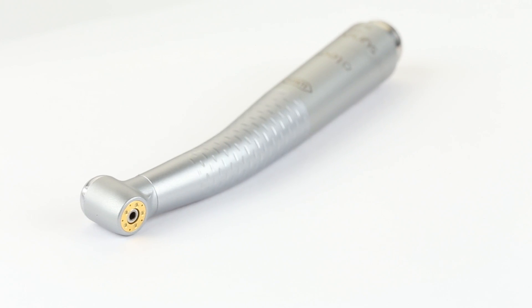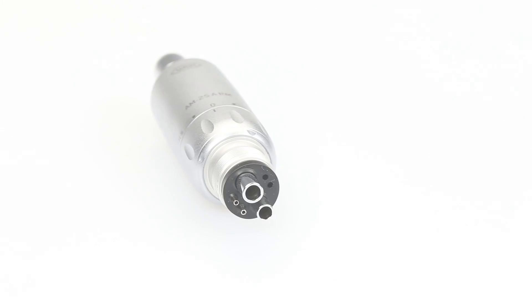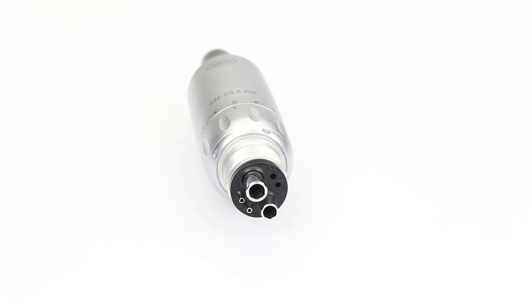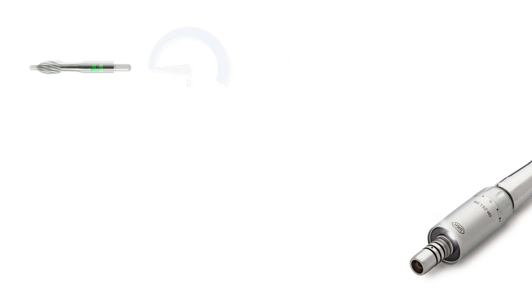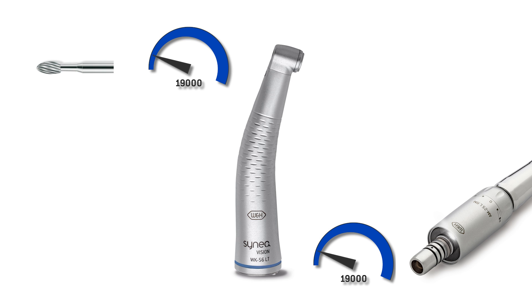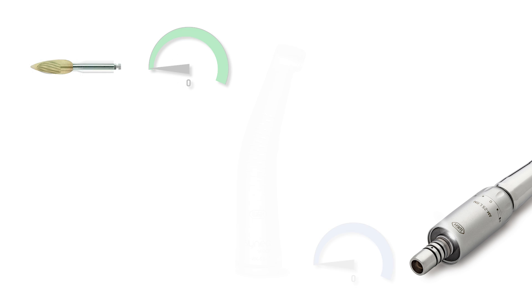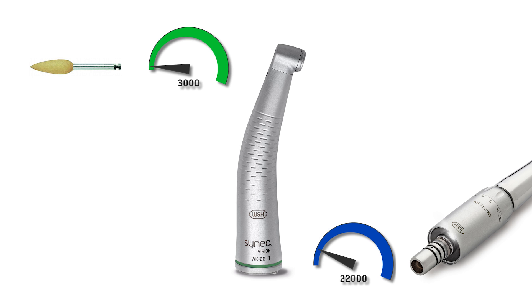Compressed air is used to drive dental turbine handpieces and air motors, which can then power green and blue straight and contra angle handpieces. Red contra angle handpieces operate faster than the drive speed, meaning the operating speed of the rotary instrument is higher than the motor speed. Blue straight and contra angle handpieces transfer the motor speed one to one, while green contra angle handpieces operate slower than the motor speed.